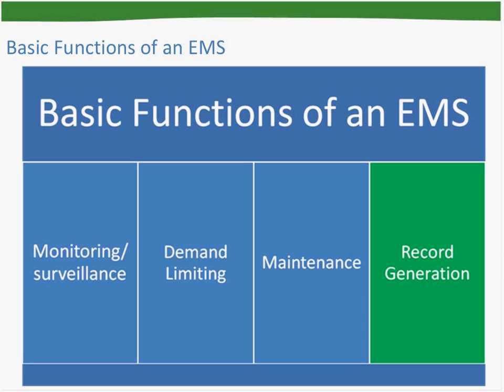Also be able to see if your schedule is actually working to help give you energy and money savings. You're also going to be able to see if the unit is actually working efficiently. We've come across in our experience of thinking that a water valve or a hot water valve may not be actually opening or closing like the equipment says it is, and spots are getting warmer and cooler than they should. Being able to look at a trend and actually see that the valve actually isn't doing anything is beneficial, just so that you can actually diagnose the problem and send us out to fix it.